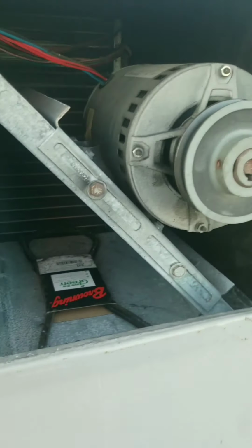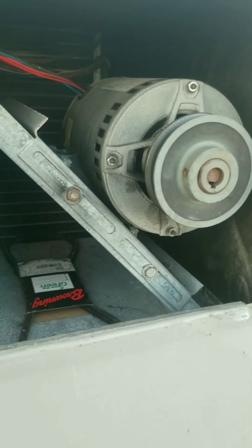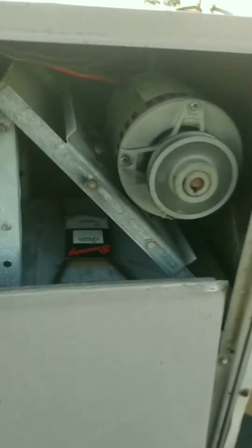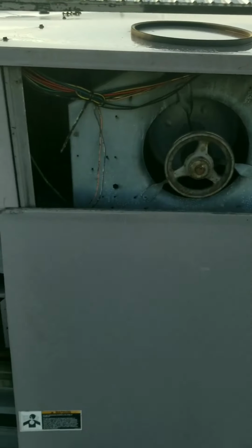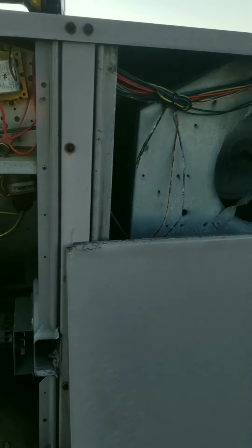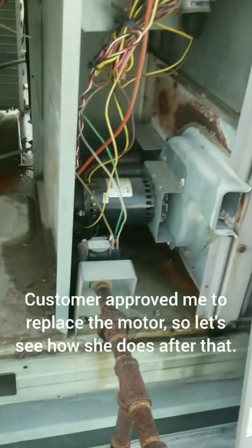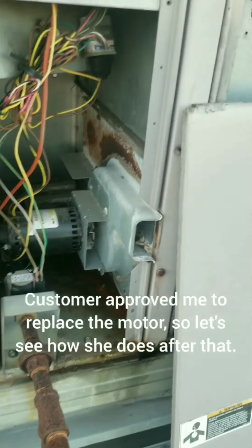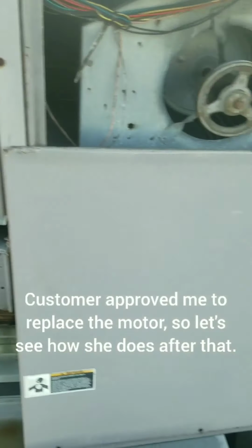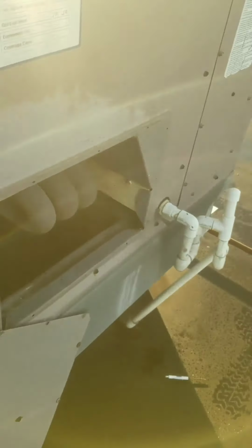So we're gonna give them an initial evaluation. They're gonna need a blower motor before I can check too much. Refrigerant circuit, not gonna be able to check without a blower motor. So we know the fan motor runs, compressor runs. We're gonna need a heat exchanger and at least a retaining plate, but the age of this unit, it's probably just gonna need to go.